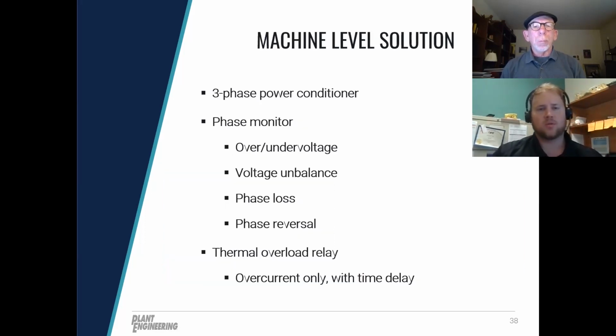If you are coordinating with your local utility, you may determine that the power quality issues are just in your facility alone, and then you may want to explore some machine level solutions. A couple options I'd like to point out on this slide are phase monitors and overload relays. Phase monitors are devices that provide protection against mainly total phase loss, phase reversal, and of course voltage imbalance. Phase monitors would be installed upstream of a critical motor or critical application, and if a blown fuse or bad connection is sensed, the phase monitor will trip the circuit and shut that motor off. That prevents the motor from seeing the single phasing event, high current across the windings, or high amounts of voltage imbalance.